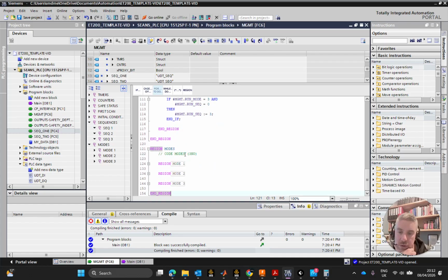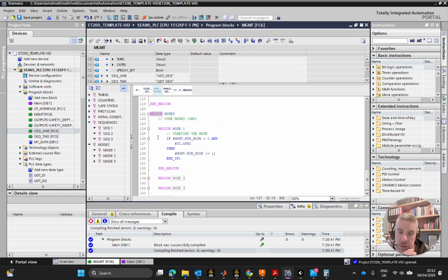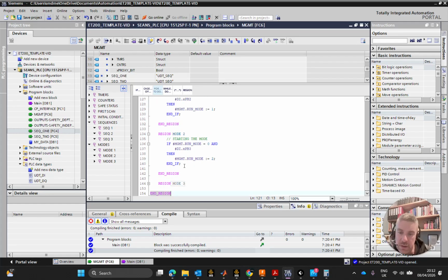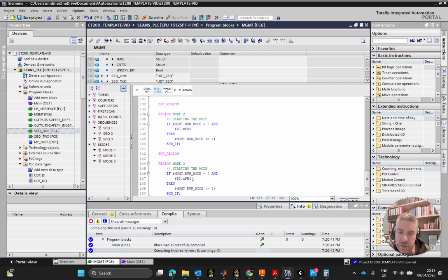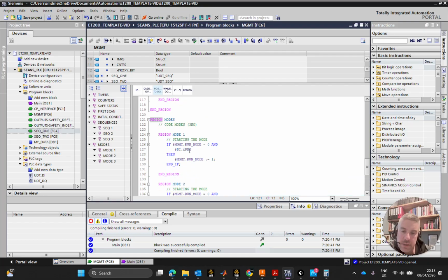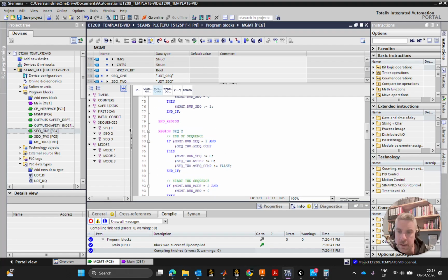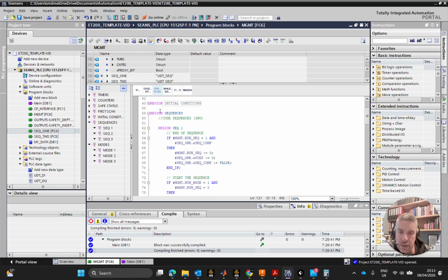Now it comes into 4, mode 1, and my run mode is equal to 0, yeah, it is equal to 0. And then it's going to keep on scanning here and looking and waiting for PB2 in this case, waiting for PB3 in this one, and waiting for PB4 in this one here. But at some stage, imagine I hit PB2, and on one scan through this, it's going to say management run mode is equal to 0 and PB2. Oh, I see that. Okay, management run mode is now equal to 1. So it goes up to the top and starts scanning again and looks in here.